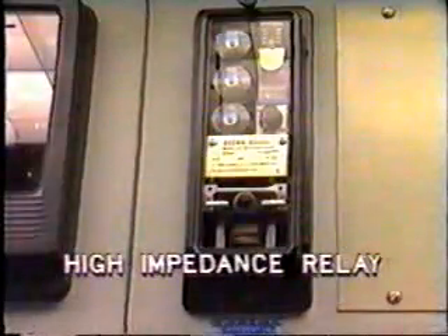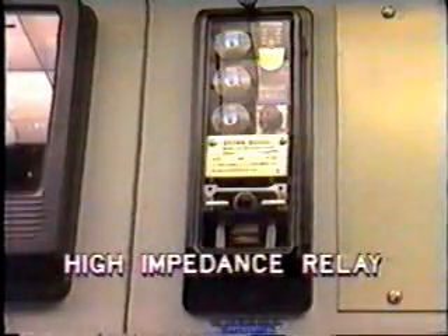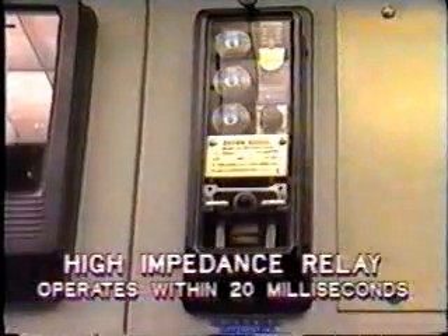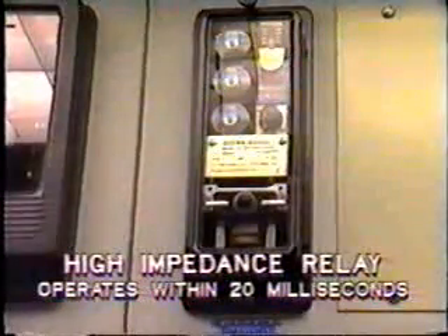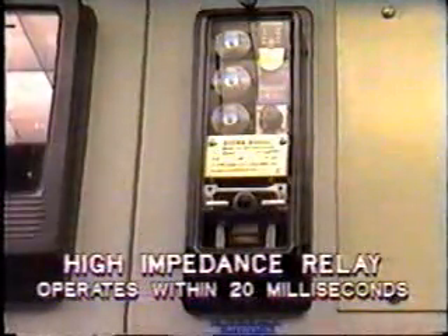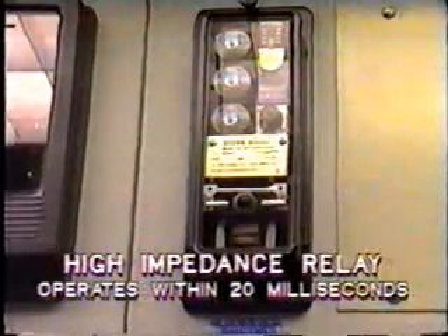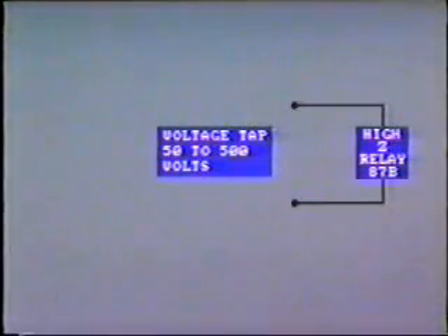The lighter bus faults will be cleared by the high-impedance relay, and this operates within 20 milliseconds. That's about 1.5 cycles. This is also extremely fast operation. The setting of the high-impedance relay is achieved by selecting the correct voltage tap, usually between 50 volts up to 500 volts.